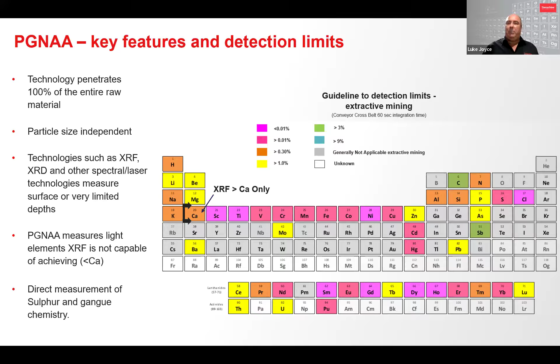Lab analyzers using these techniques require analysis under vacuum or in a helium-purged environment to measure light elements accurately, which is obviously not possible for online measurement. PGNAA, however, can accurately measure both heavy elements above calcium and lighter elements online, enabling real-time analysis of sulfur and light elements associated with gangue, which impact process control and metal recovery. So measurement technique alone does not ensure a solution that works.